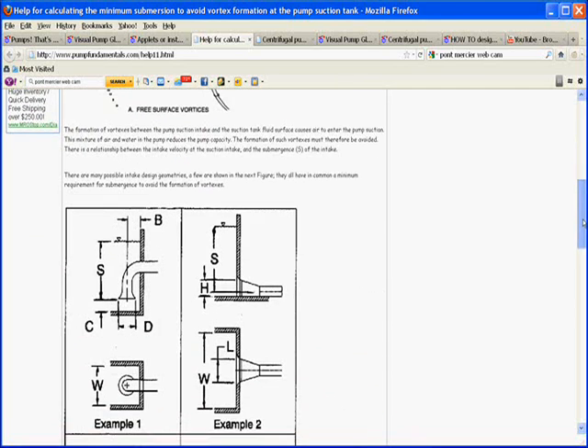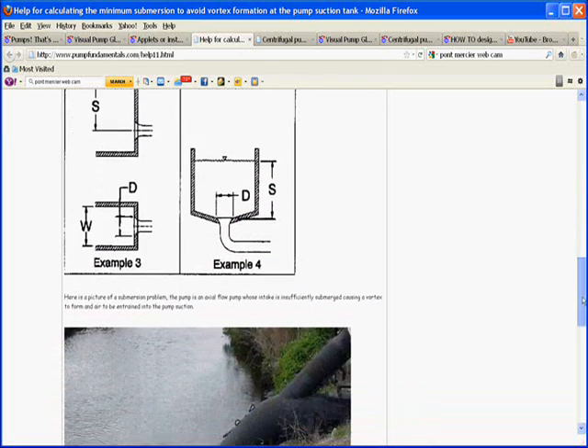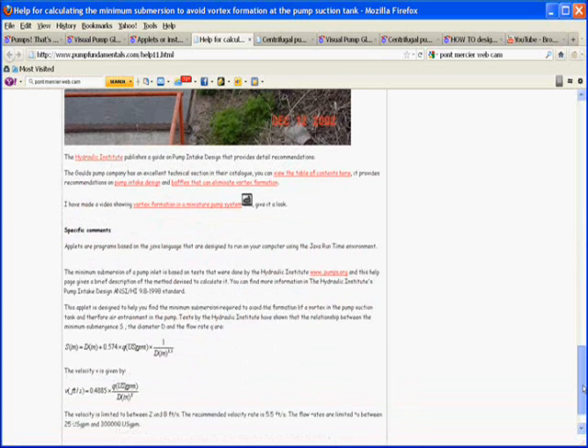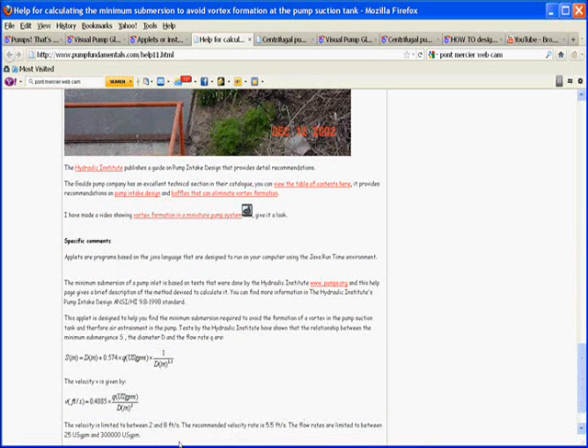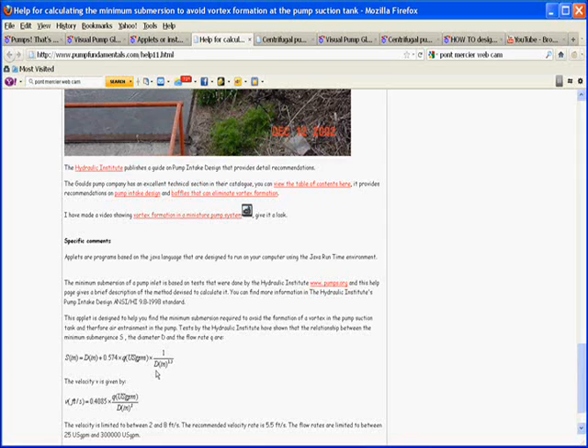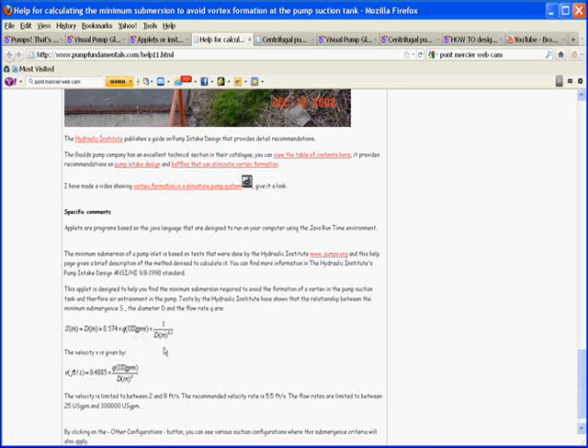But the equation that predicts the formation of a vortex is quite simple. The height of the liquid between the surface and the suction pipe, so the submergence level is S, and that will be equal to the diameter of the suction pipe times this constant here times the flow rate over the diameter of the suction pipe. So if you plug your numbers in here, flow and diameter, you'll get the minimum submergence height.